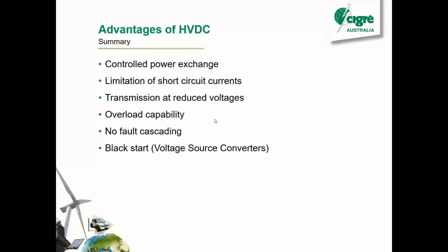Yep. So yeah, some more advantages. Yeah, that controlled power exchange that I was just talking about. You can limit your short circuit currents. If you'd used an AC network connection, you can increase the fault level, which can be a bad thing that can end up costing you more in gear. With HVDC, you're not gonna do that. It's completely separated.